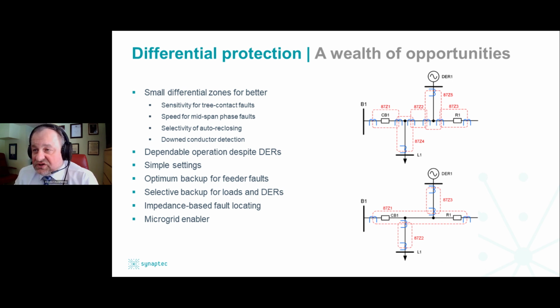So the figure on top shows that I divided my feeder into small differential zones, where each section, either of the main trunk or the laterals, is protected with an individual two-terminal differential zone. The figure at the bottom shows that I may choose to protect the main trunk with a larger zone and then each lateral with its own differential zone. So my fault detection is becoming much more granular and also sensitive. My tripping zone, of course, is limited by the current interrupting devices that I have there.